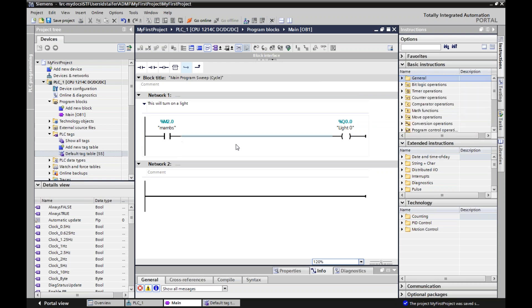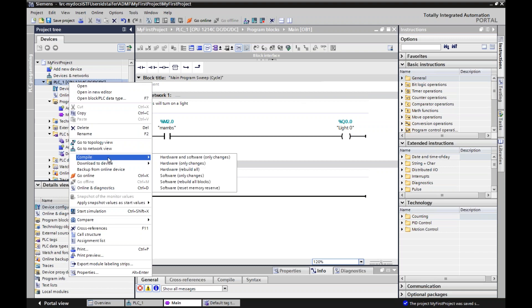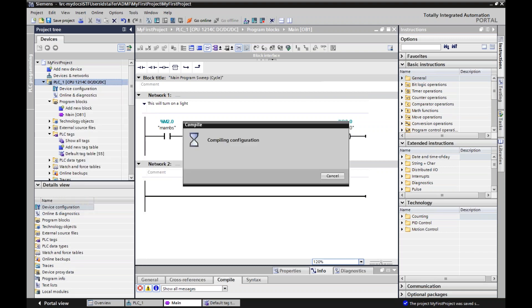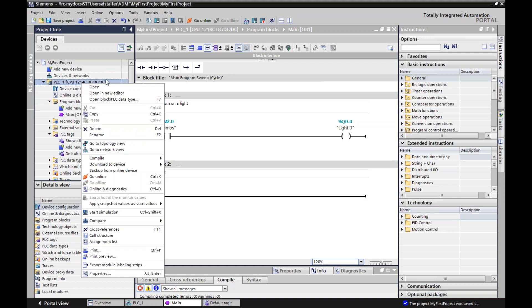So now that I have a basic program, all I have to do to go online is once again, over PLC, I can right click, compile. I'm going to rebuild all software blocks because that just makes sure that everything gets clearly rebuilt. And what compiling does is packages the software in a way so that it's compressed and easy to read for the PLC. So it's not just taking up a bunch of random memory bits all over the controller.